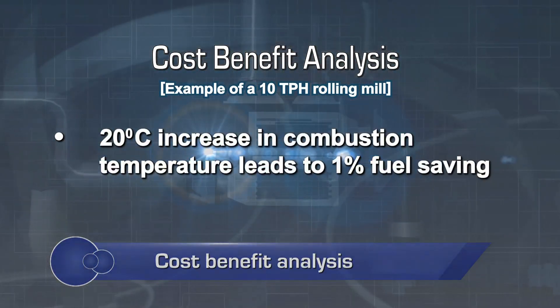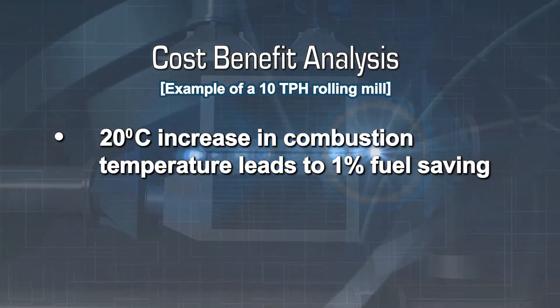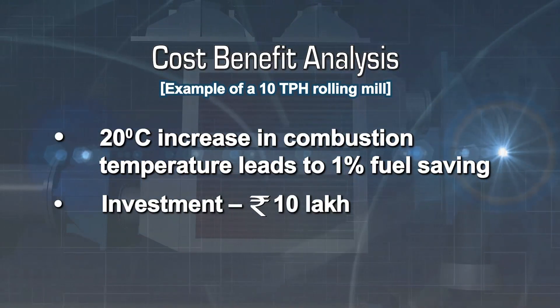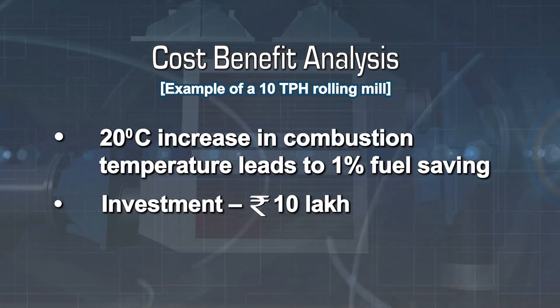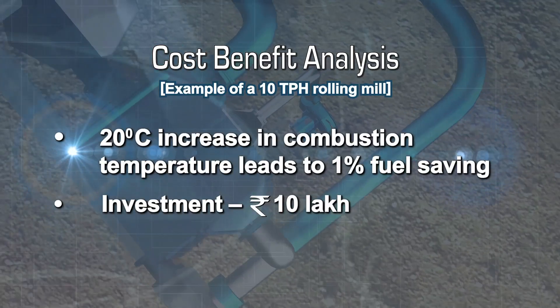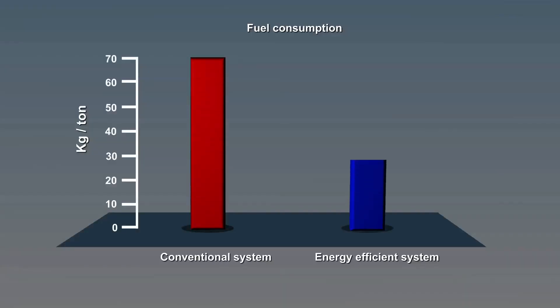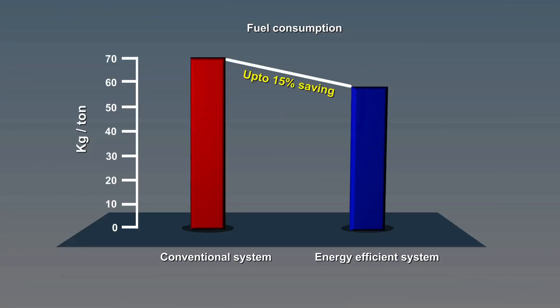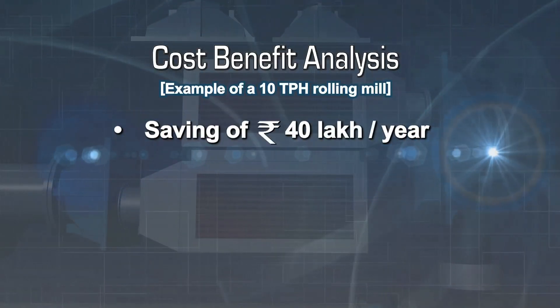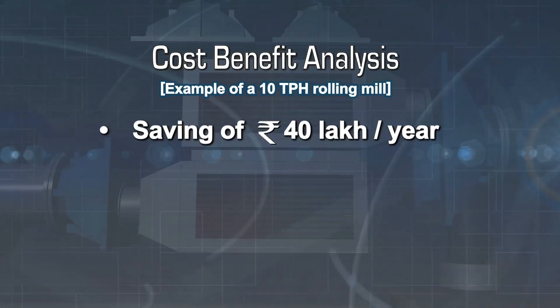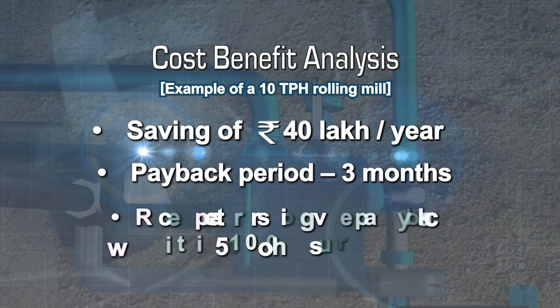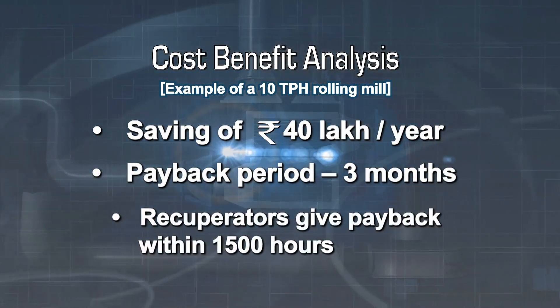Every twenty degrees Celsius increase in combustion air preheat temperature leads to a fuel saving of one percent. Investment in a recuperator varies with its effectiveness. A high efficiency recuperator for a ten TPH furnace would cost around ten lakhs, leading to a saving in specific fuel consumption of fifteen percent annually. A ten TPH plant will save around forty lakh rupees, so the investment can be recovered in less than three months.